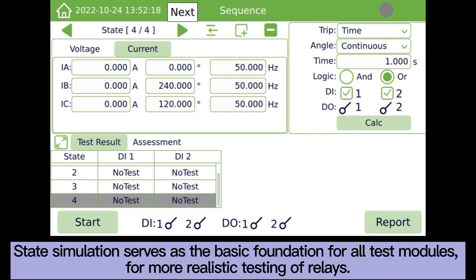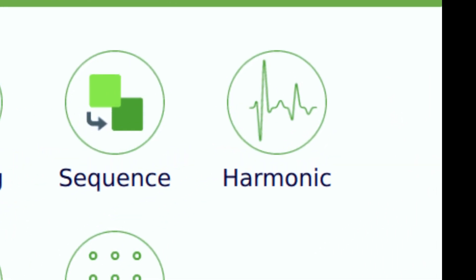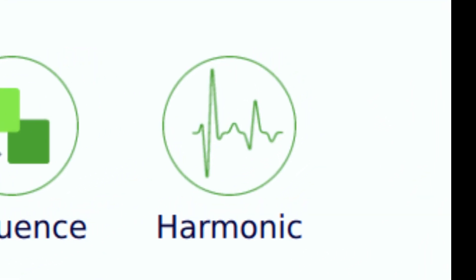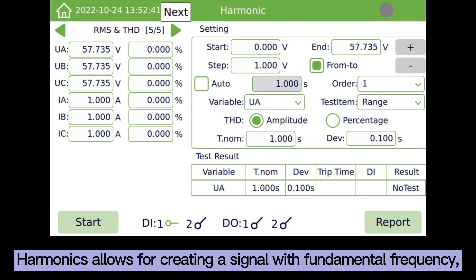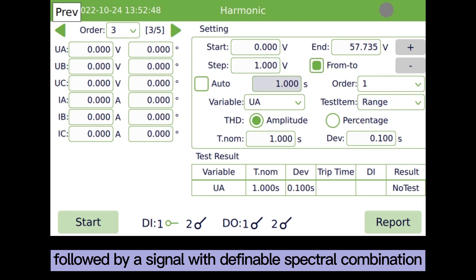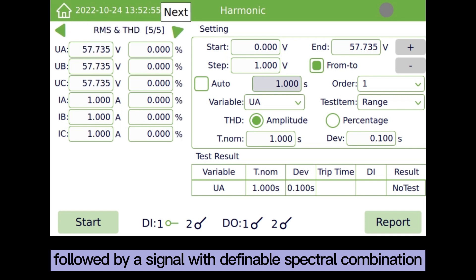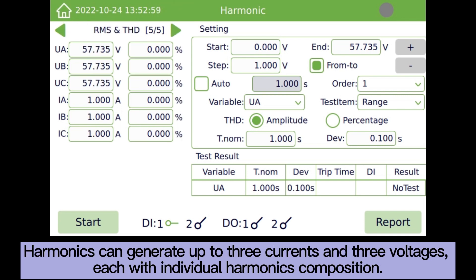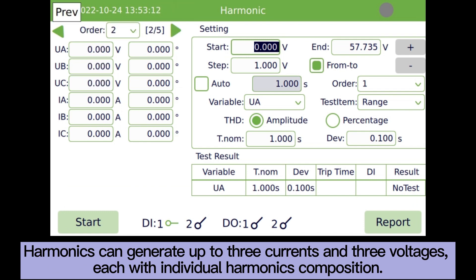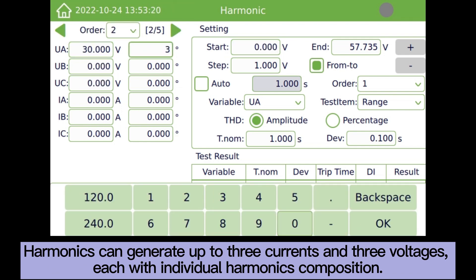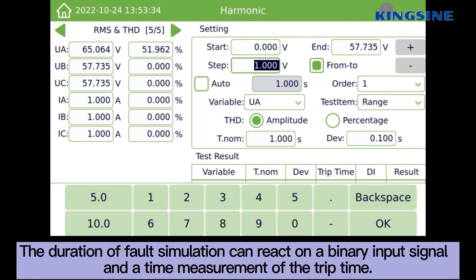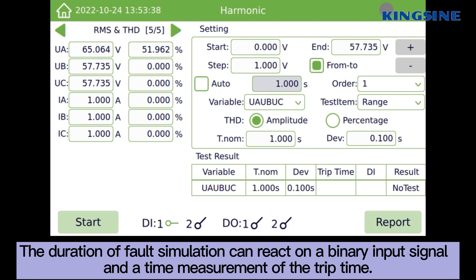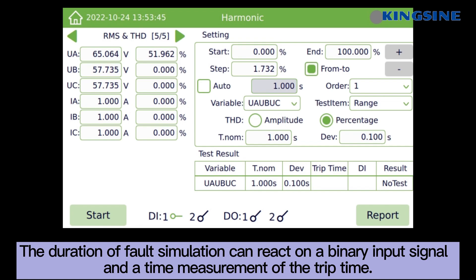For more realistic testing of relays, the harmonics module allows for creating a signal with a fundamental frequency, followed by a signal with a definable spectral combination. Harmonics can generate up to three currents and three voltages, each with individual harmonics composition. The duration of fault simulation can react on a binary input signal, with time measurement of the trip time.